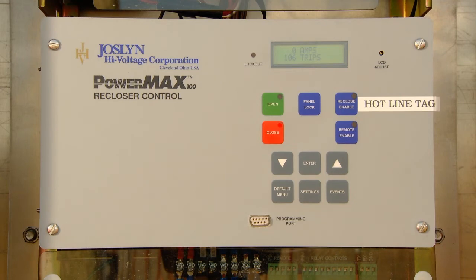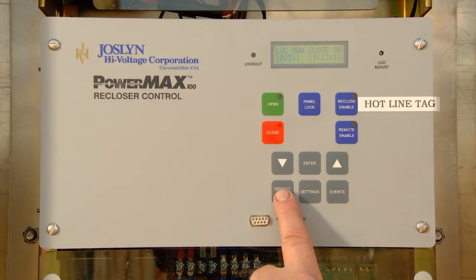Pressing the Events button will display the most recent operation. This screen, for example, shows that the most recent operation was a manual close. Had this been a faulted condition, the actual fault records would be displayed. To leave the Events display, press the default menu button.